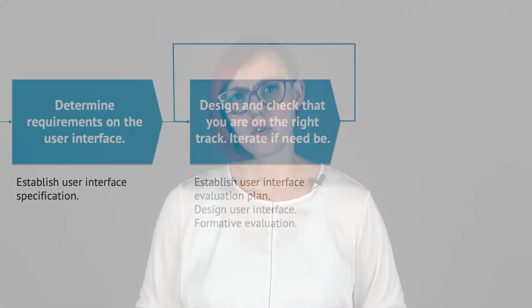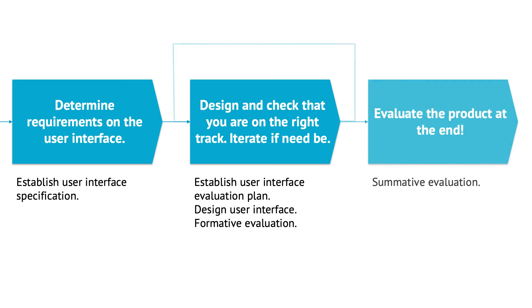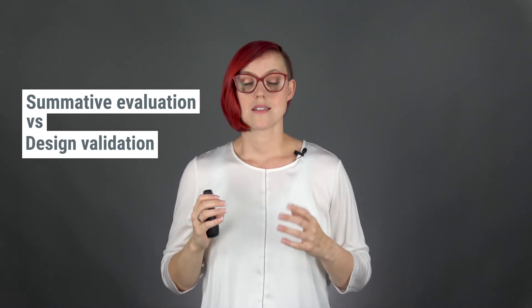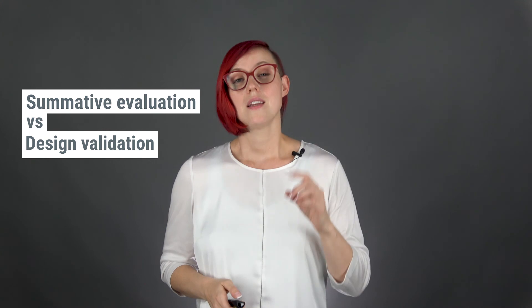If you find you are not on track, you need to iterate on the design and improve. You proceed until your last formative test shows nothing more to improve. After implementing the user interface according to requirements and evaluating it along the way, it's time for the final summative evaluation. The summative evaluation demonstrates that the user does not end up in a situation with unacceptable risk as a result of poor usability. Note that it is not the same as design validation — design validation shows user needs have been met, while summative evaluation shows the user interface is safe.